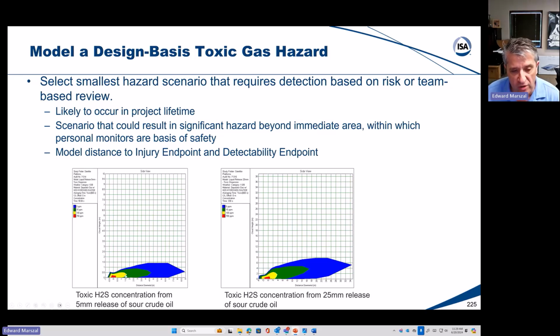So we would want to be able to detect the gas cloud. So if I could overlay the dirty bubble over top of this, its diameter would be from 0 to 4.7 meters. And again, we did that based on dispersion modeling. And in this case, we're actually looking at what size of gas clouds we expect to occur at your facility.